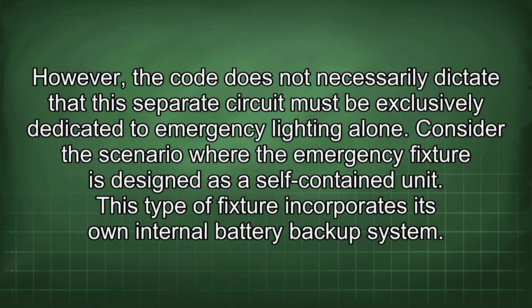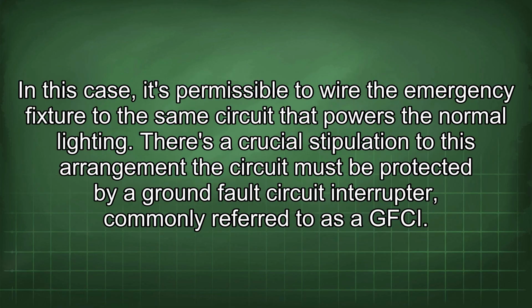This type of fixture incorporates its own internal battery backup system. In this case, it's permissible to wire the emergency fixture to the same circuit that powers the normal lighting. There is a crucial stipulation to this arrangement: the circuit must be protected by a ground fault circuit interrupter, commonly referred to as a GFCI.